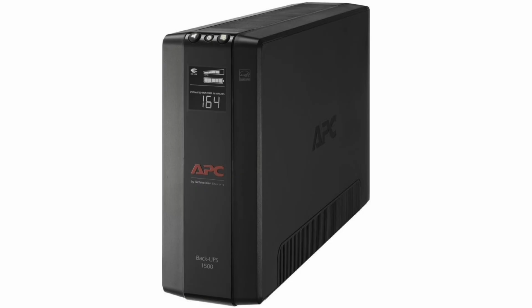That said, in the case of this Back-UPS 1500 or whatever it is, the capacity of 1500 watts, asterisk VA, volt-amperes, is what the unit can be expected to drive as its maximum load. That's how much work it can be doing at any given moment and presumably still function as designed. Don't exceed that, and the device won't be working so hard that it can't keep the battery charged, for instance.